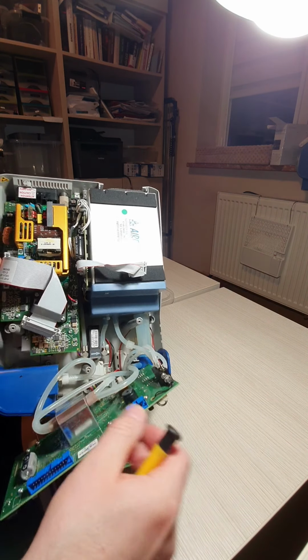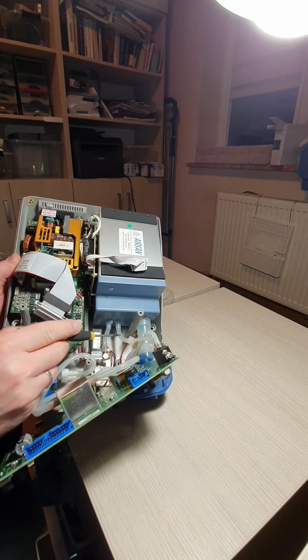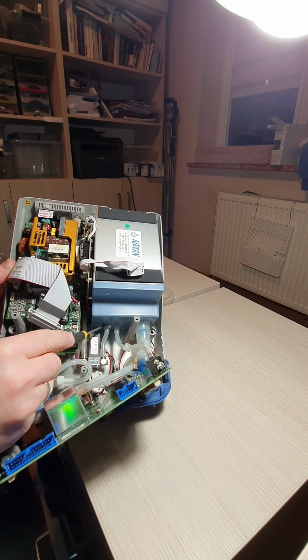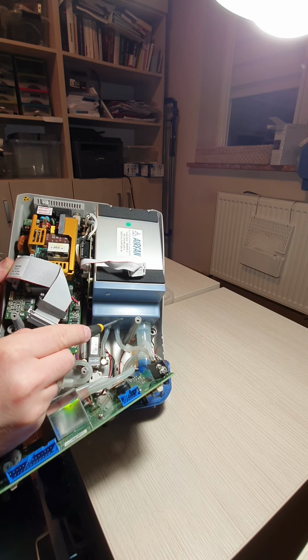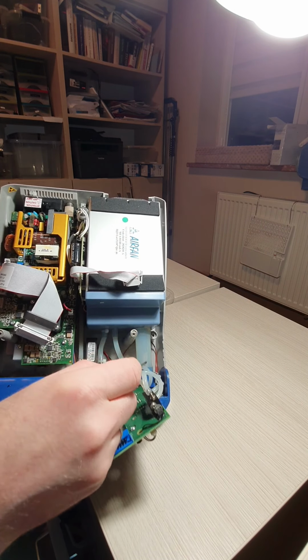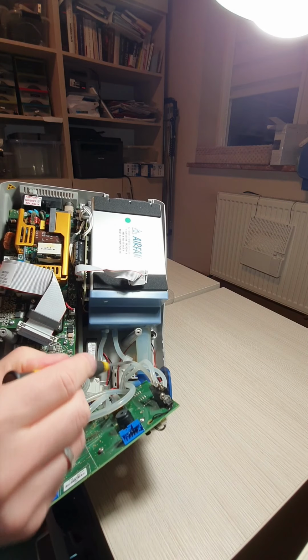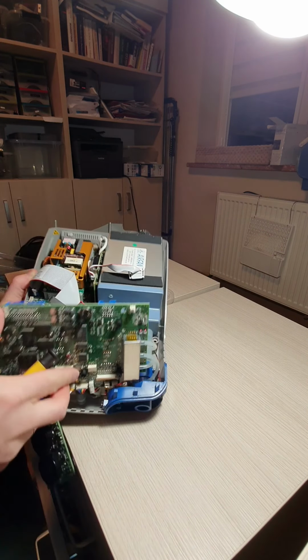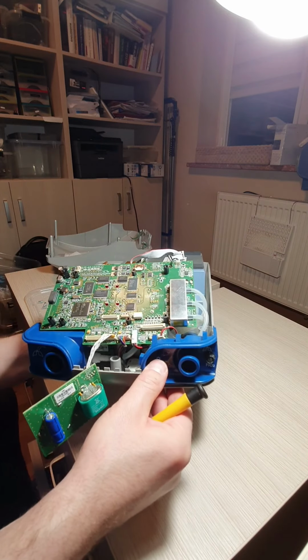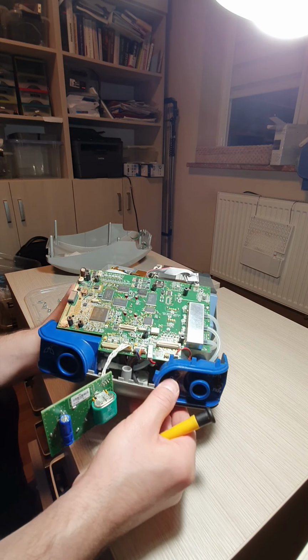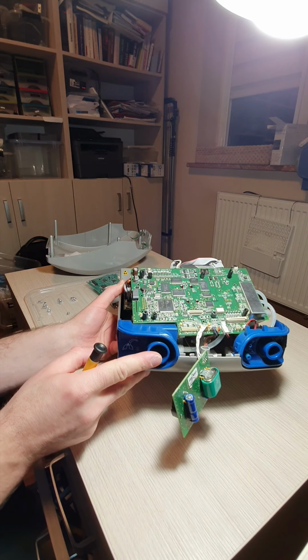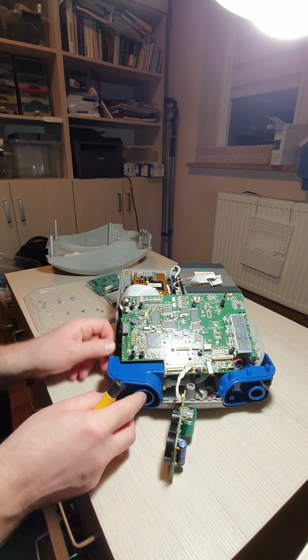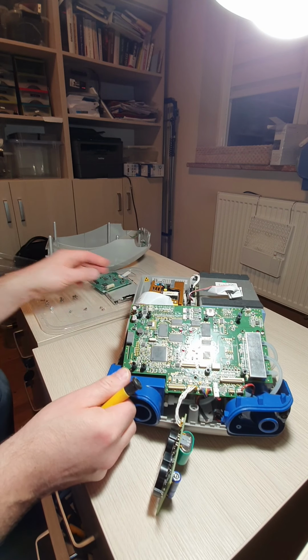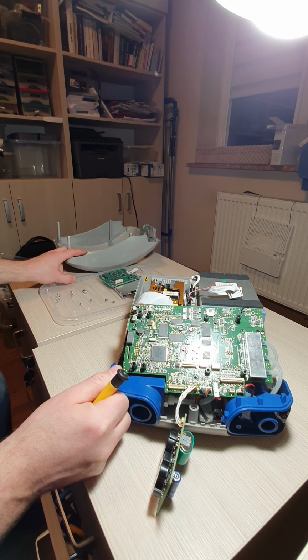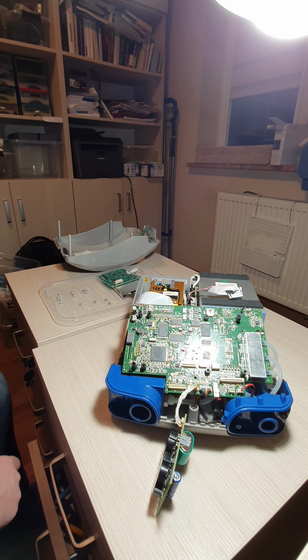Actually, what it does, it simply controls this. This is the place where oxygen is dosed by the valve. It's mixed with the air, and this is the air. The air goes out, and also this air goes through this valve to the port here, where the external exhalation valve is connected. The valve is actually connected to the exhalation port, and it simply opens in such a way that the pressure does not drop to zero. The function is called PEEP, whatever it means.